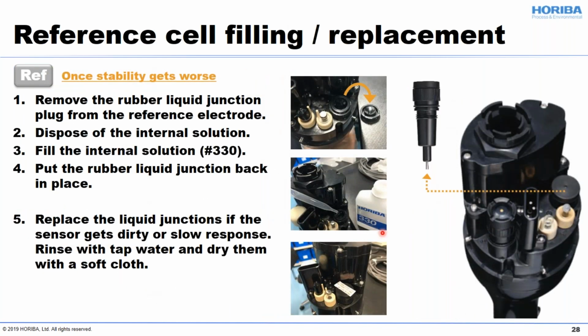Reference electrodes are also very easy to replace. If the internal solution in the reference electrode is worn out, you can add internal solution inside. It's detachable by finger — open the cap and fill it with internal solution. Our model number is 330; just close the cap afterward. But sometimes the junction gets dirty, and in that case, please rinse it with tap water and dry it with a soft cloth.